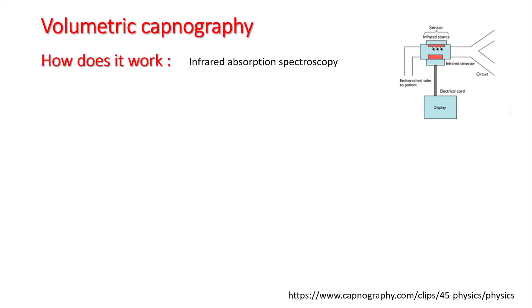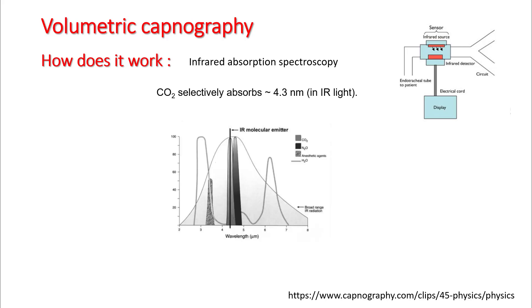The other method is volumetric capnography. Volumetric capnography can give you the value of the PCO2. Carbon dioxide selectively absorbs at around 4.3 micrometer width, which lies in the infrared region of light. So your CO2 concentration depends upon the absorption at this wavelength.